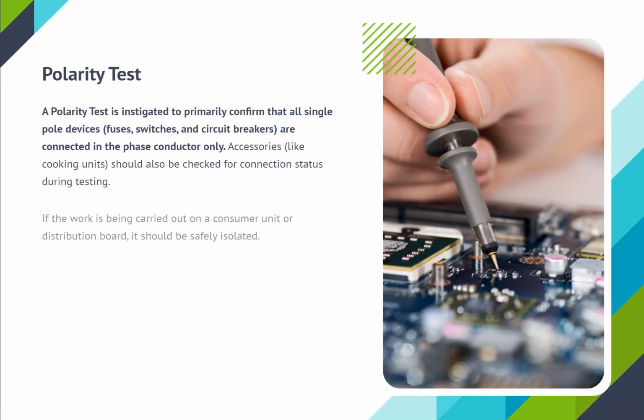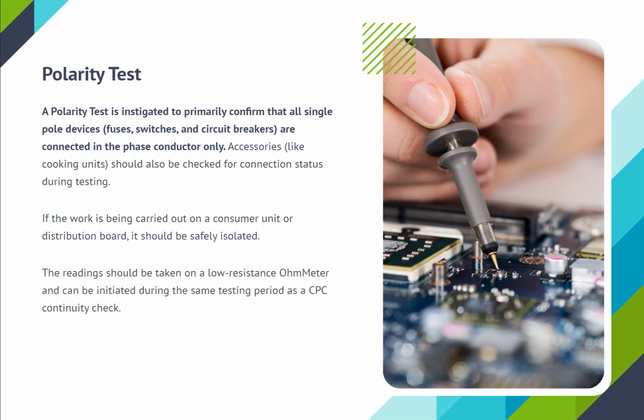Polarity test. A polarity test is instigated to primarily confirm that all single-pole devices, fuses, switches, and circuit breakers are connected in the phase conductor only. Accessories, like cooking units, should also be checked for connection status during testing. If the work is being carried out on a consumer unit or distribution board, it should be safely isolated. The readings should be taken on a low resistance ohm meter and can be initiated during the same testing period as a CPC continuity check.